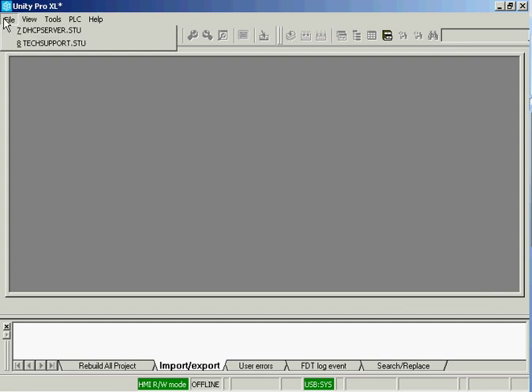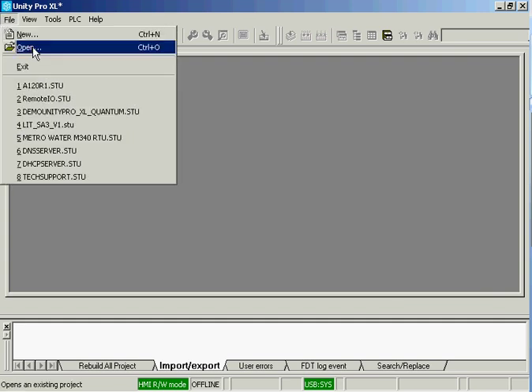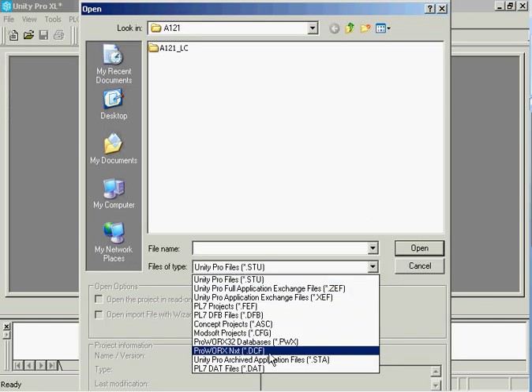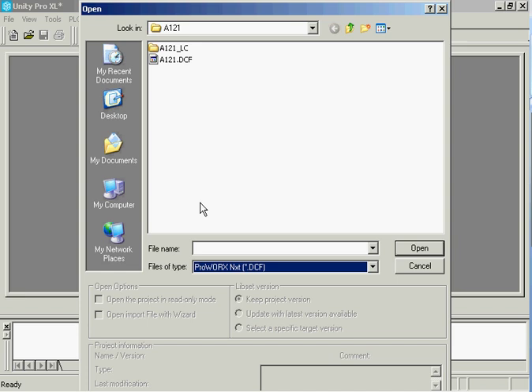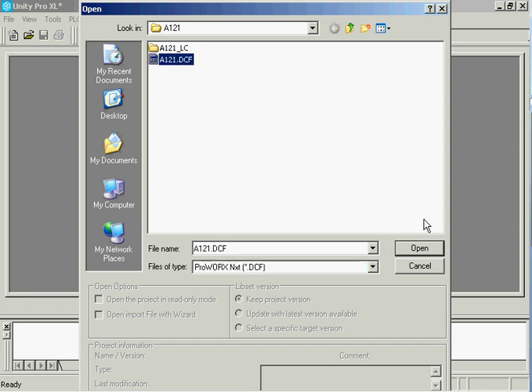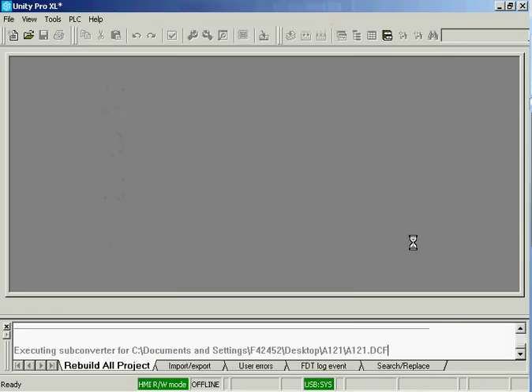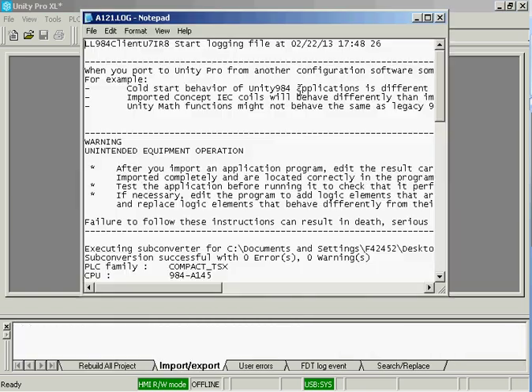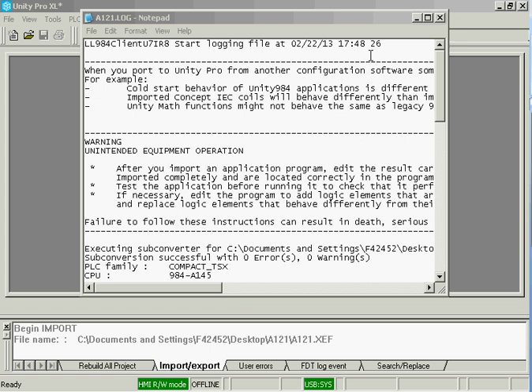is to open a project. We're going to open an NXT project that's a Compact 984 and convert it into an M340. The symbols will be my tag names, and I'm going to use Modbus or flat addressing in case an HMI or another PLC was talking to this unit.